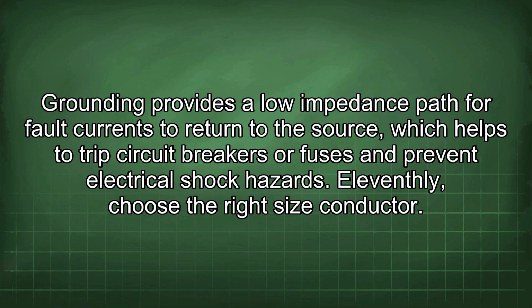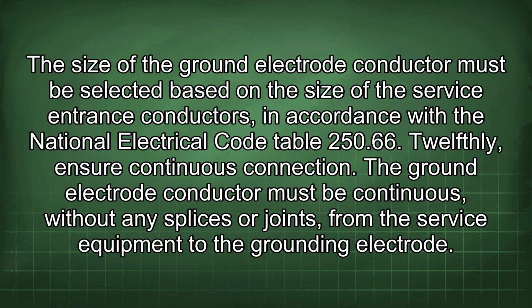11thly, choose the right size conductor. The size of the ground electrode conductor must be selected based on the size of the service entrance conductors, in accordance with the National Electrical Code Table 250.66. 12thly, ensure continuous connection. The ground electrode conductor must be continuous, without any splices or joints from the service equipment to the grounding electrode.